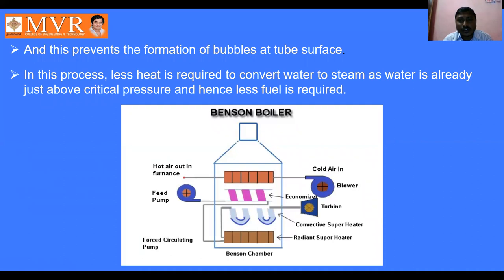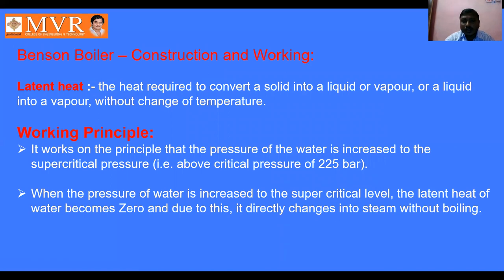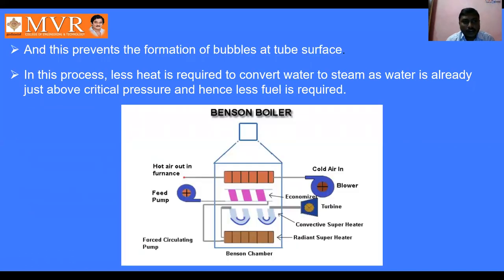In this process, less heat is required to convert water to steam, as water is already just above critical pressure, and hence less fuel is required for the combustion process. So to summarize: in the Benson boiler, the pressure is increased up to 225 bar, the water is directly converted into steam without boiling, bubbles are not formed, and the fuel and heat required are very less.